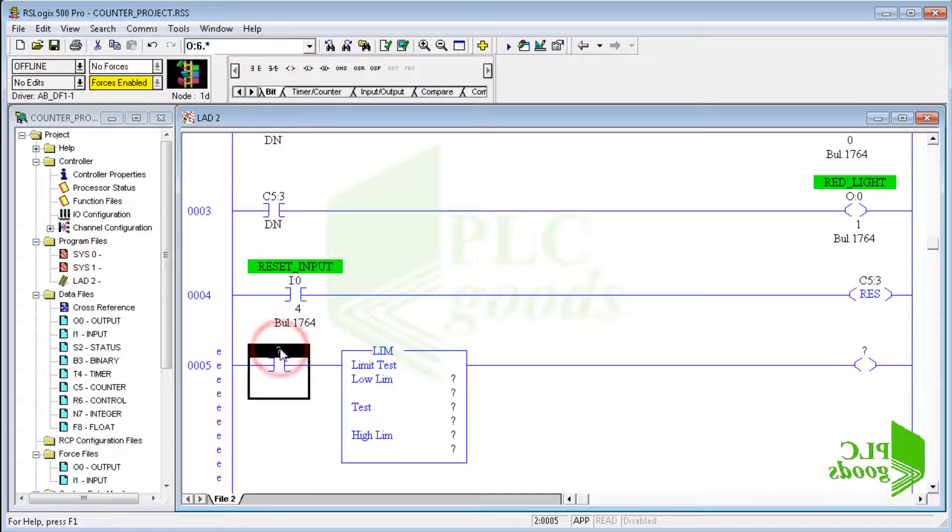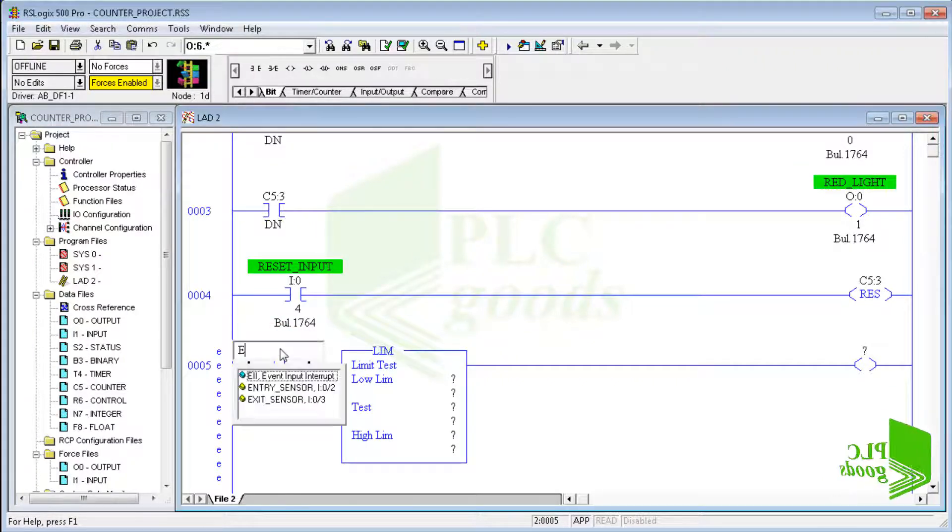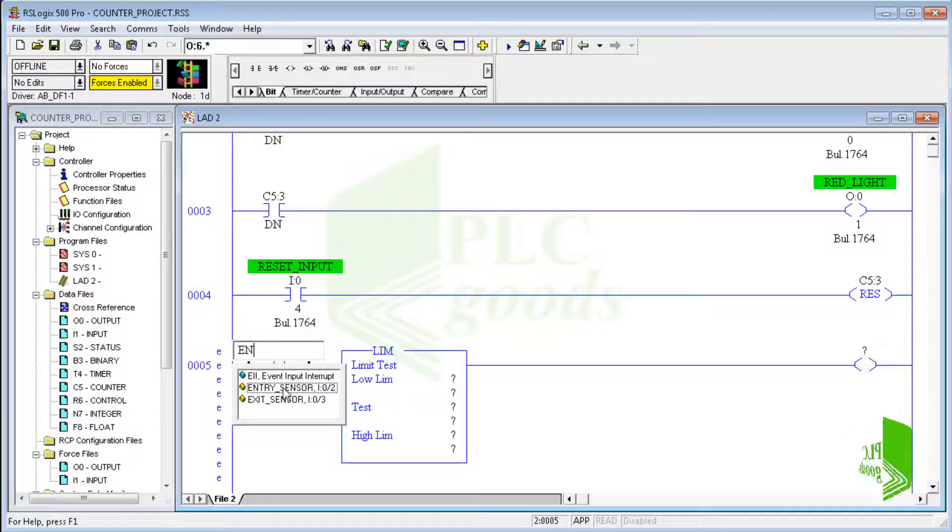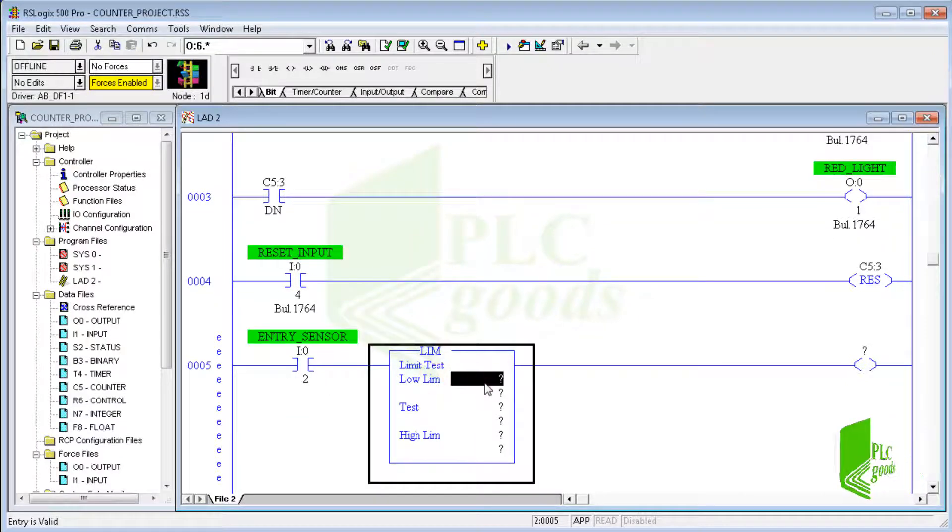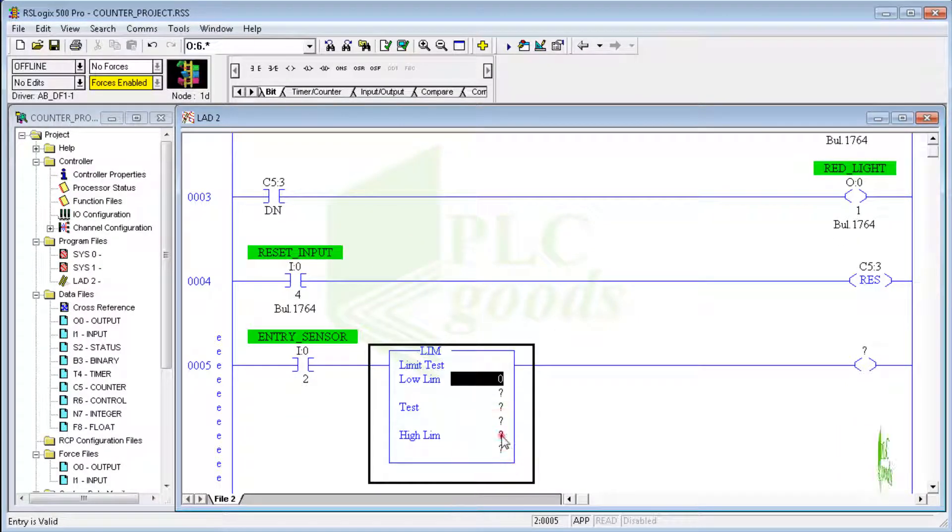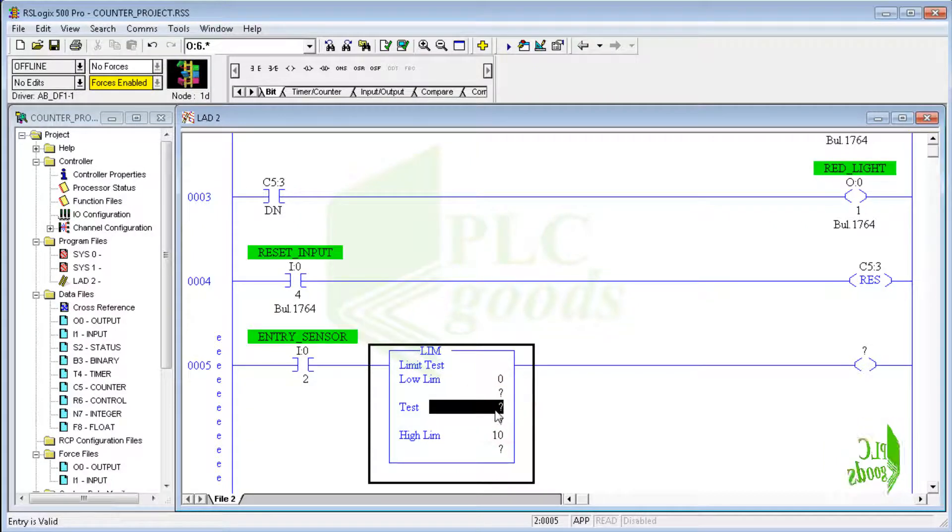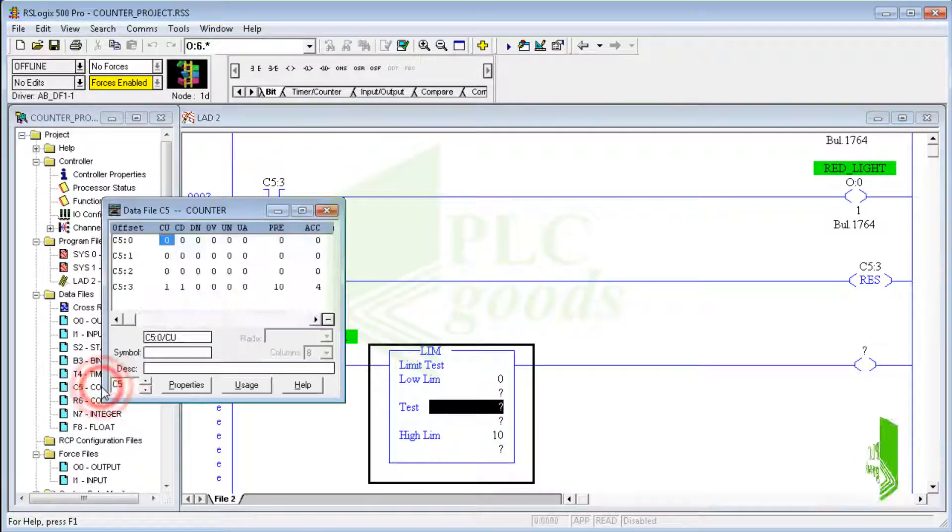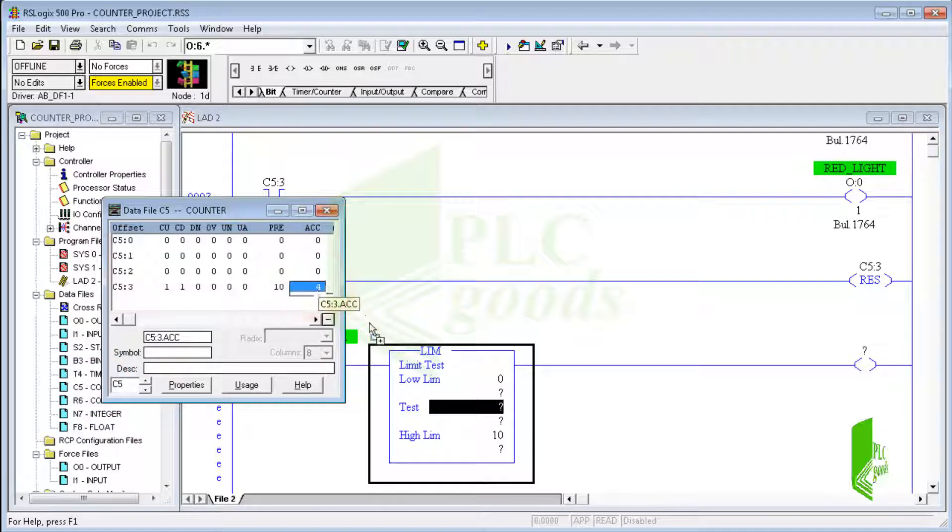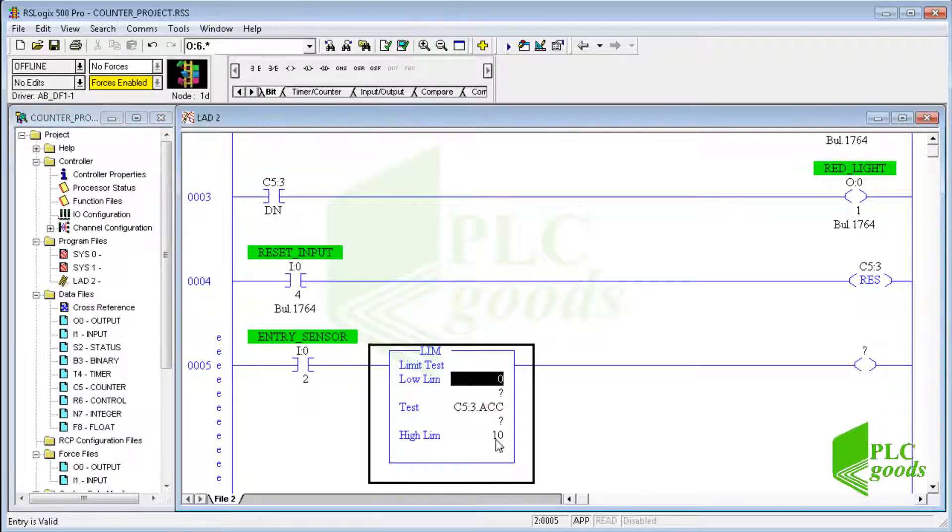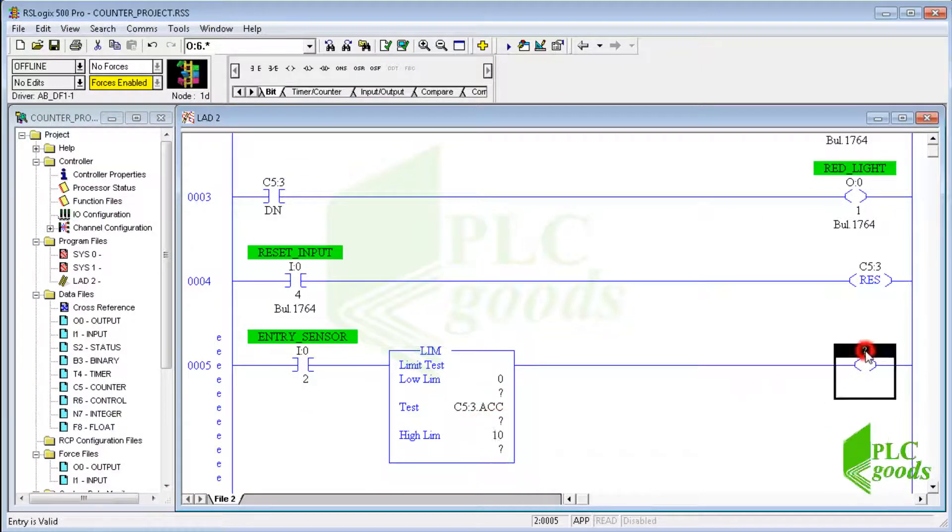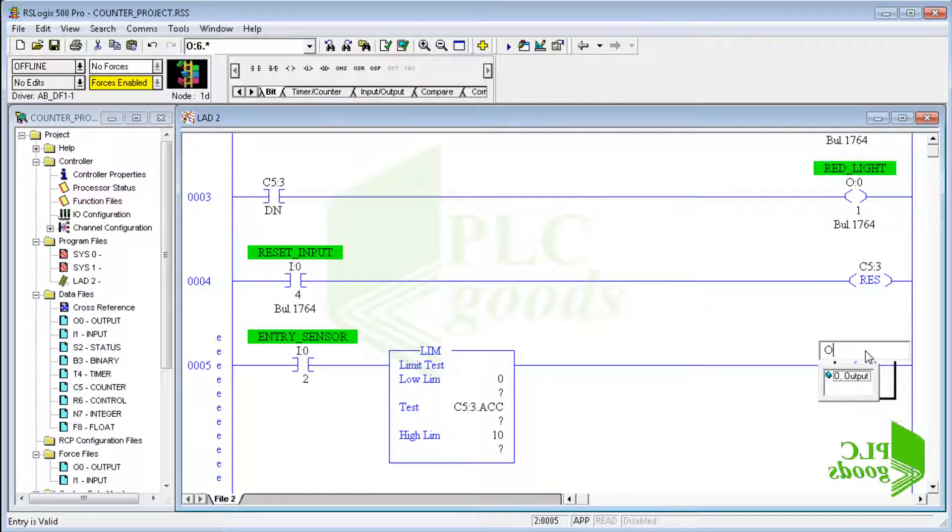A limit test instruction can be used to check the parking lot capacity. So I use the entry sensor address for this contact. Before, I defined a symbol for this input, so I can use its symbol instead of its address. I write 0 and 10 for the low and high limits, and the entry gate can be opened when the accumulated value is in this range. Finally, I use the third output to open the entry gate.